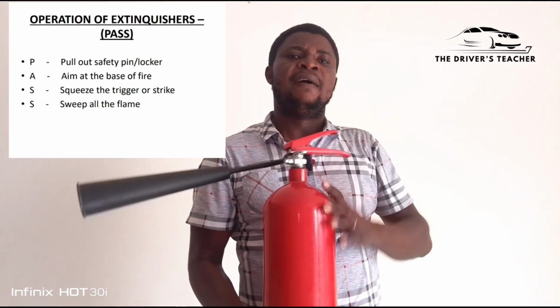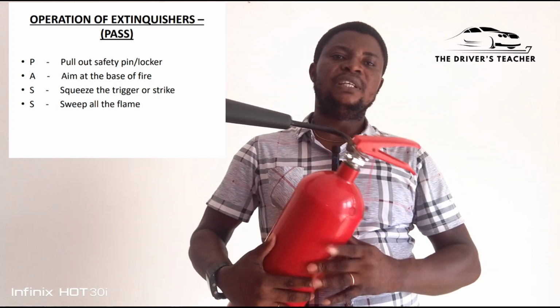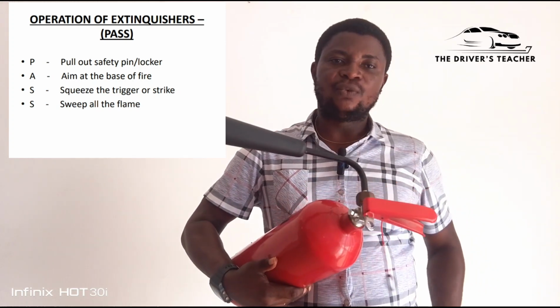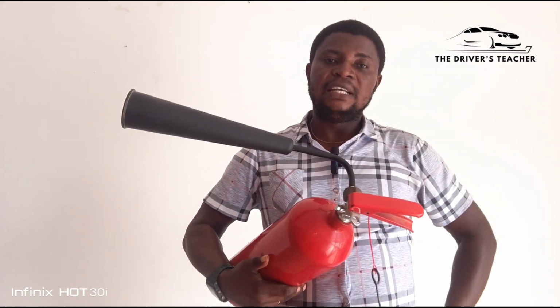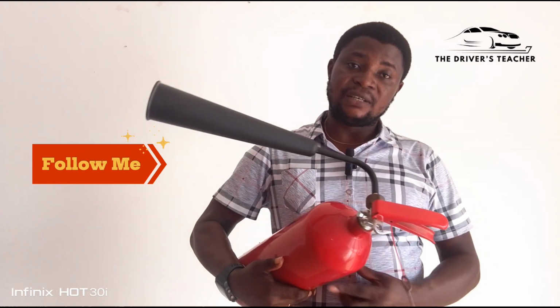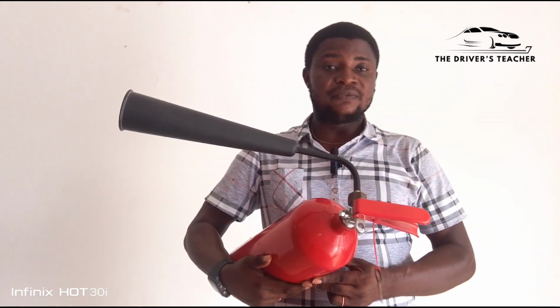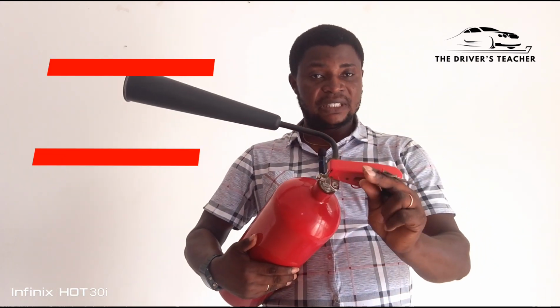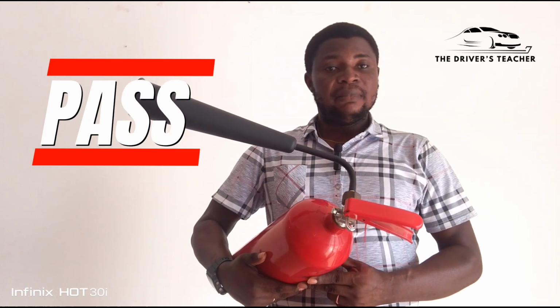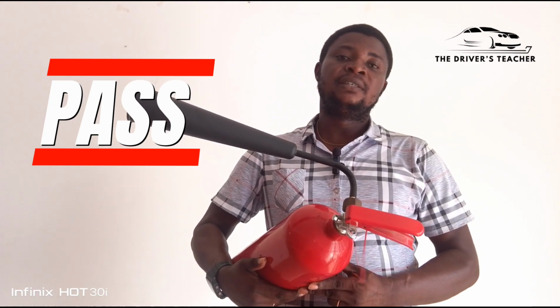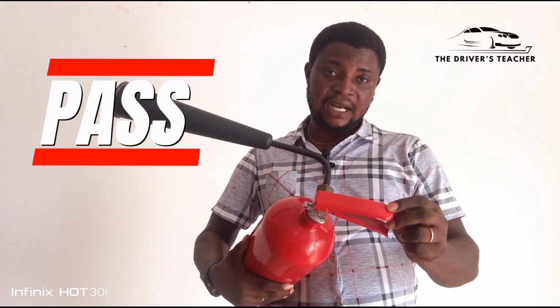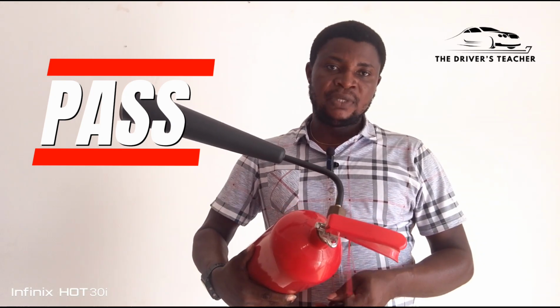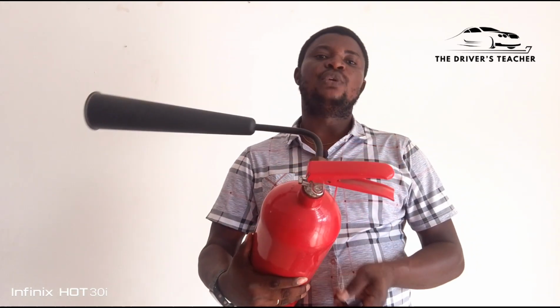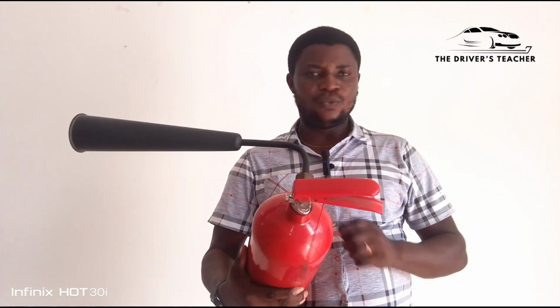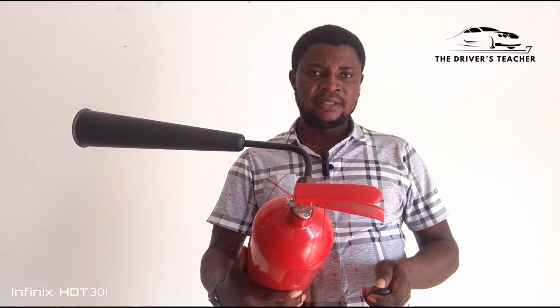So always make sure you go by using the PASS method whenever you are turning off fire using a fire extinguisher. The first one stands for pull out the safety pin, which is this. Aim at the base of the fire, then squeeze the trigger or the locker, then sweep the flame. In the course of doing that, you can turn off the fire easily without any difficulties.